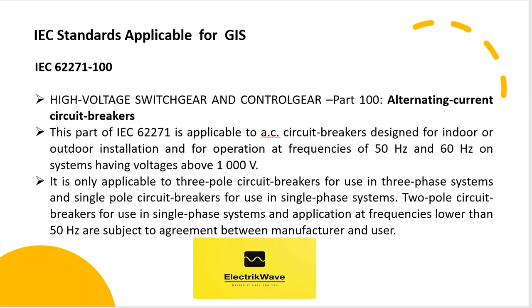IEC 62271-100: High Voltage Switchgear and Control Gear, Part 100, Alternating Current Circuit Breakers. This part of IEC 62271 is applicable to AC circuit breakers designed for indoor or outdoor installation and for operation at frequencies of 50 Hz and 60 Hz on systems having voltages above 1000 V. It is only applicable to 3-pole circuit breakers for use in 3-phase systems and single-pole circuit breakers for use in single-phase systems. 2-pole circuit breakers for use in single-phase systems and application at frequencies lower than 50 Hz are subject to agreement between manufacturer and user.